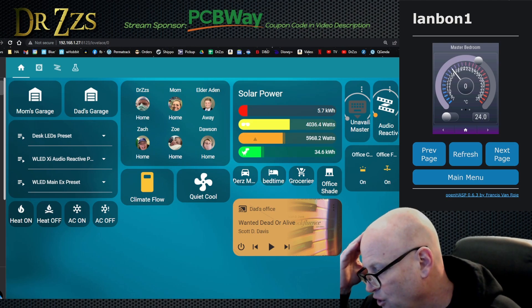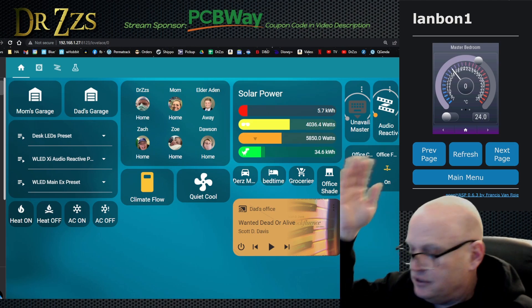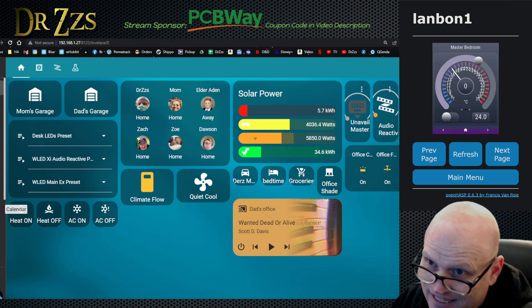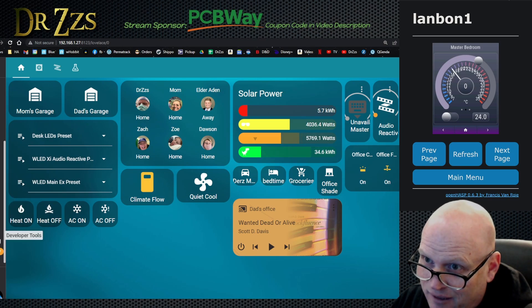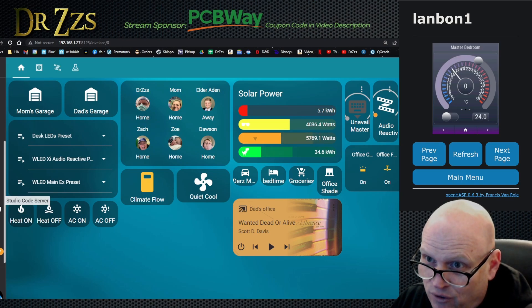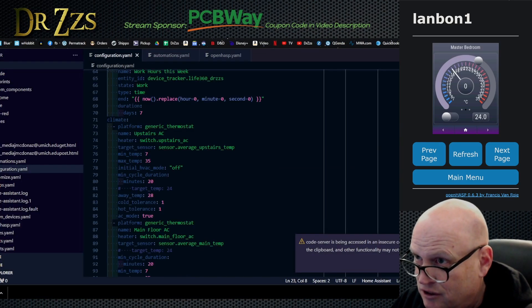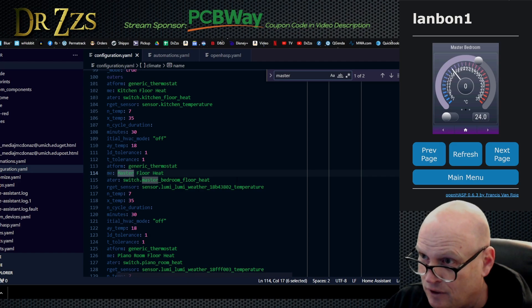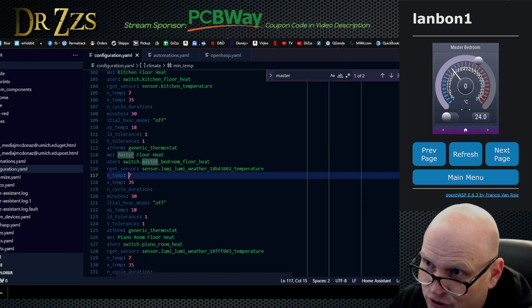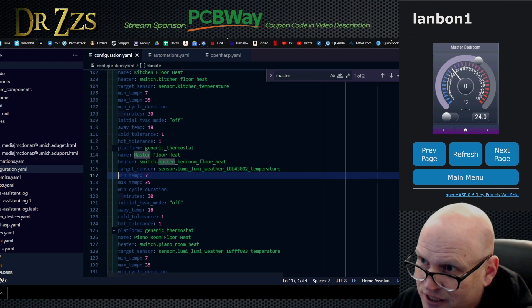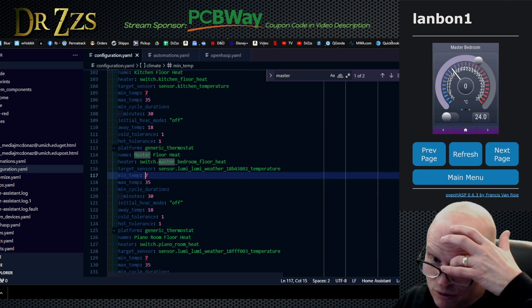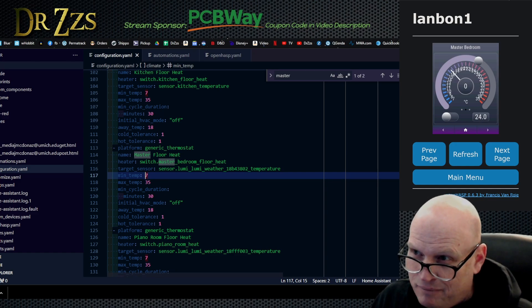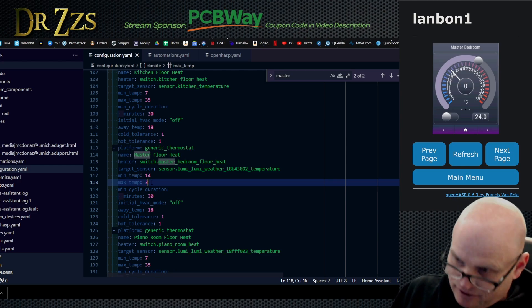So there's a few things going on here. One is our display - the numbers on that display are going from seven to 35. I'm going to guess that's because that's what my climate entity is telling it to do. So we're going to go into Visual Studio, go into the configuration, find that master floor heat. Here it is - it goes from seven to 35, minimum temp seven, maximum temp 35. I don't think we need minimum seven, maximum 35. What's the minimum in Celsius you'd ever set your air conditioning to? Maybe 14, and the maximum can be like 30.